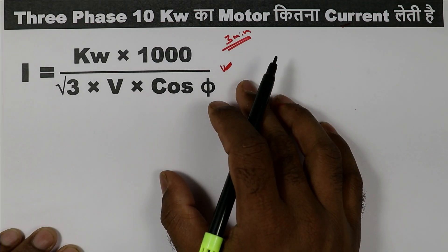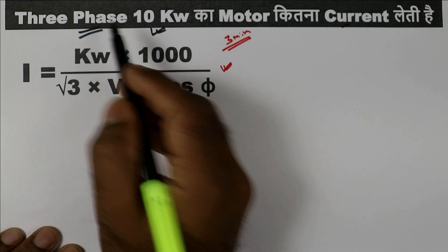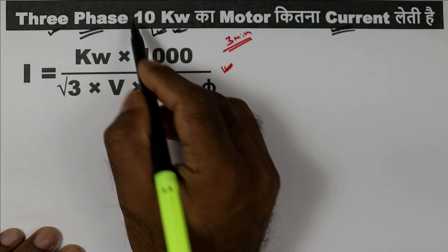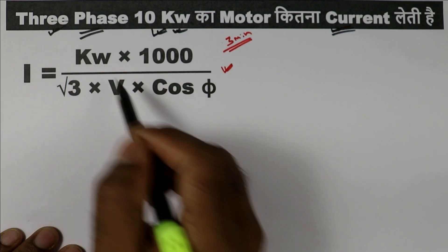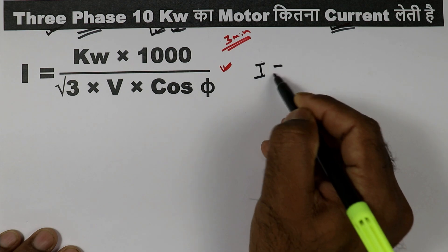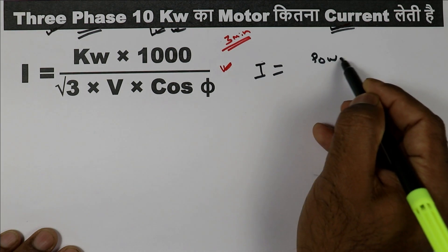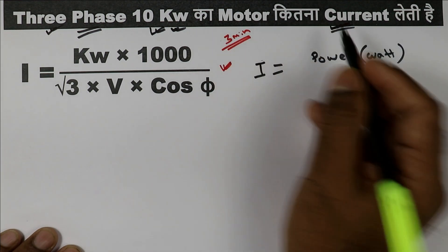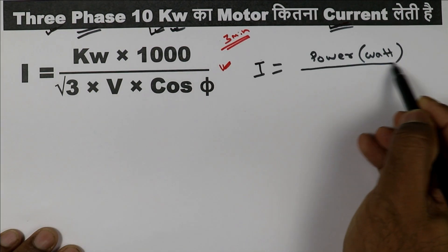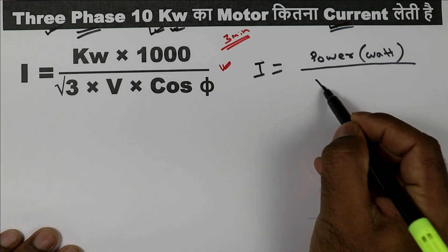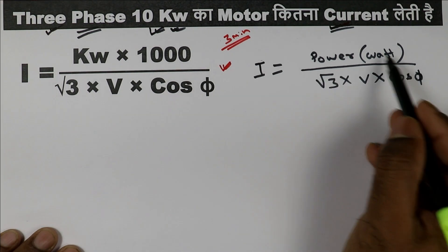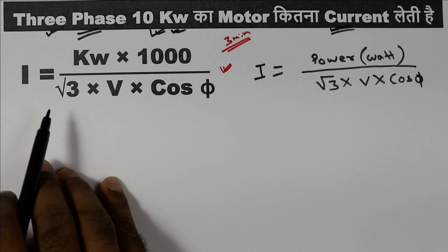Suppose in your interview you were asked to find the current rating of a 10kW 3-phase motor. If the question is in kW and it is for 3-phase, you have to use this formula: I equals power in watts divided by root 3, multiplied by voltage, multiplied by power factor. So by using this formula, you can find the answer.